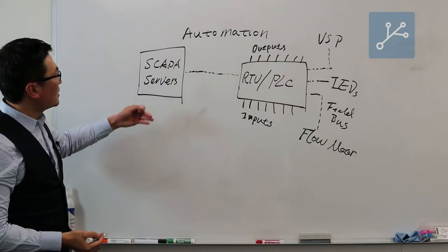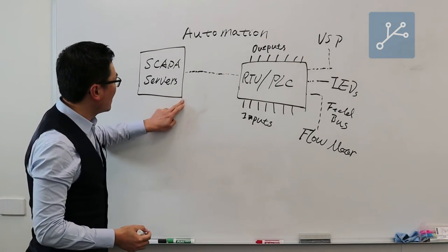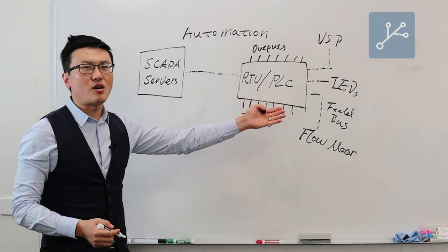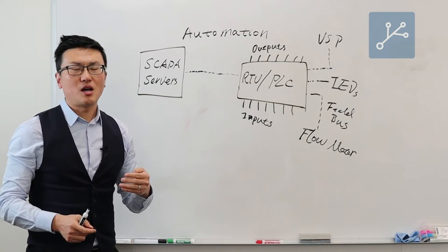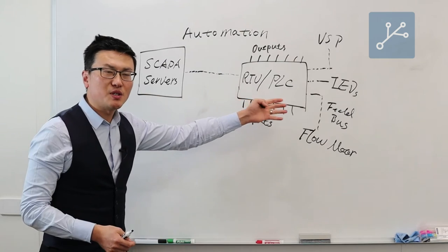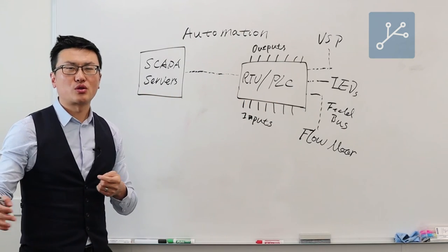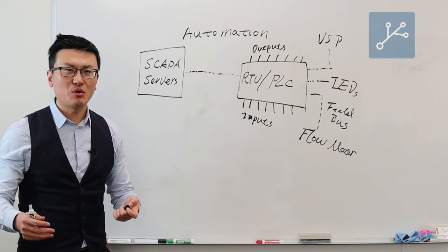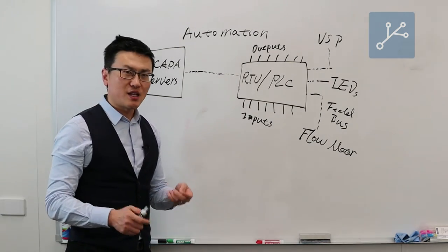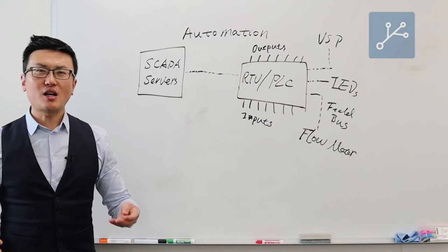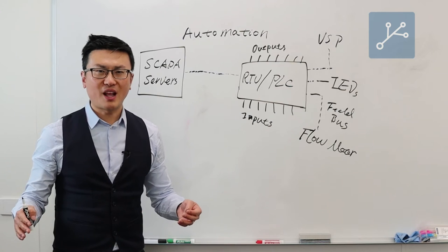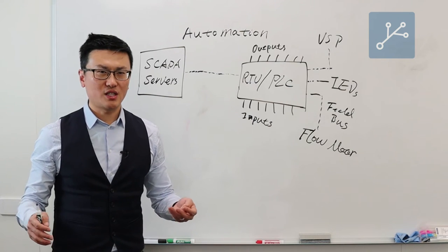In the old days, the SCADA server was located very close to the control system, the PLCs or RTUs. They could be a few meters away, a couple of hundred meters away. So the linkage between these two components can be done through hardwired cable, Ethernet, or fiber optics. And it's still the case for some sites, such as local factories, manufacturing plants, or a mining facility.